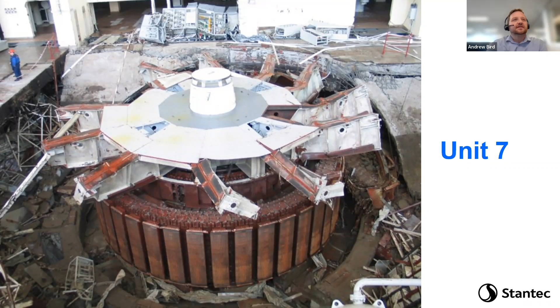Okay, so the next one's around the 2-minute closure time on the intake gates. Was this based on what all the intake gates can handle when closing under full flow, or was a full redesign required for the gates? I do not know, but the 2 minutes is too fast in my opinion. That is really fast for gates of this size and this type of flow and head. We normally tell the turbine designers that they're supposed to design for up to 30 minutes of these types of high-speed events. But a normal closure for us is about a meter per minute, so at 10 meters, you'd be looking at 10 minutes to close an intake gate like this.